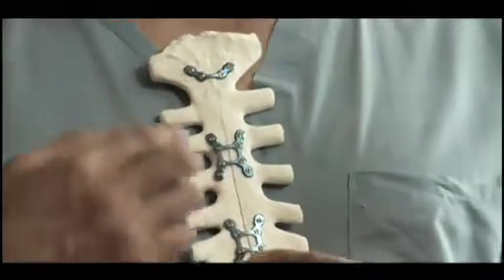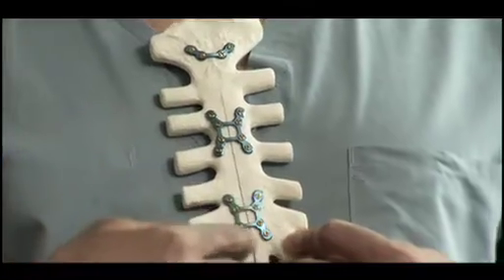Dr. Jay Raman demonstrates how the Sternalock system works and how it can be used with less invasive approaches. We use plates this way, and the plates are anchored using these golden screws that anchor onto the bone itself. If we have to do a mini-sternotomy — splitting just a part of the sternum using an inverted T incision — we break this part of the bone, and when we bring the fragments back together, we fix them with plates and these screws.